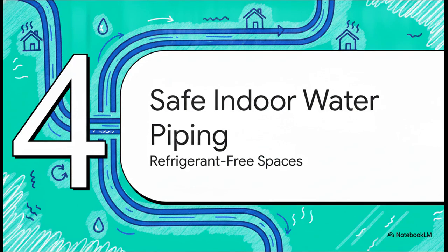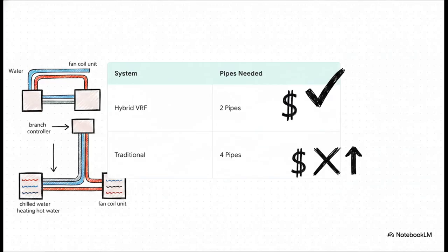Which leads us perfectly into Section 4, safe indoor water piping. Look at the sheer simplicity of this. Since we are using water now, you've got options. Piping can be run in standard copper or even polyethylene, depending on the manufacturer. But the real kicker is the comparison. You only need 2 pipes running between the branch controller and the fan coil. If you were doing this with a traditional chilled and hot water system, you'd be running 4 pipes.